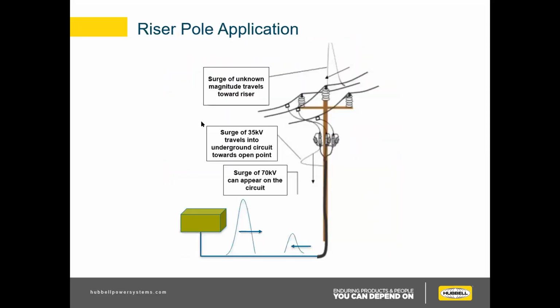So now we're going to talk a little bit about riser poles. This is where you really can get into trouble with installation coordination. For a second, let's say we do not have an elbow arrestor in this. This is a pad mount transformer, like the little green boxes. So we don't have an arrestor here, and this is an open circuit, so a breaker's open in here somewhere.